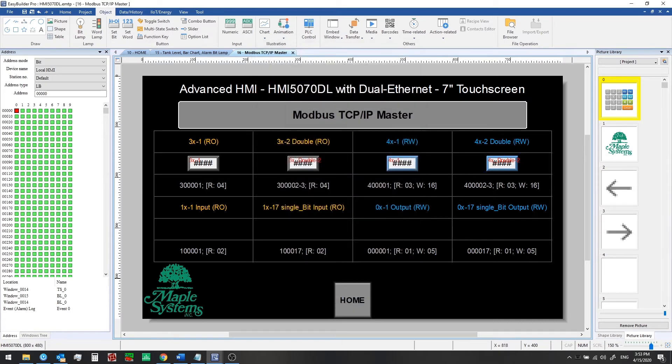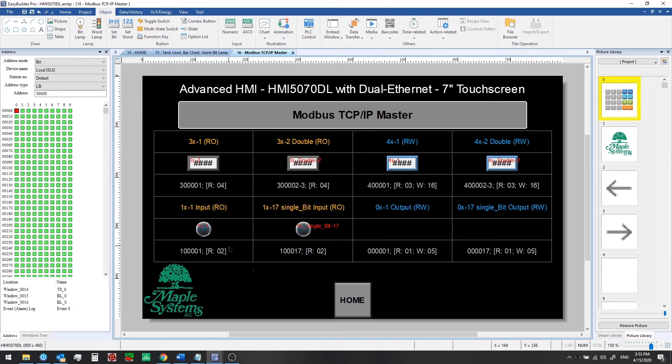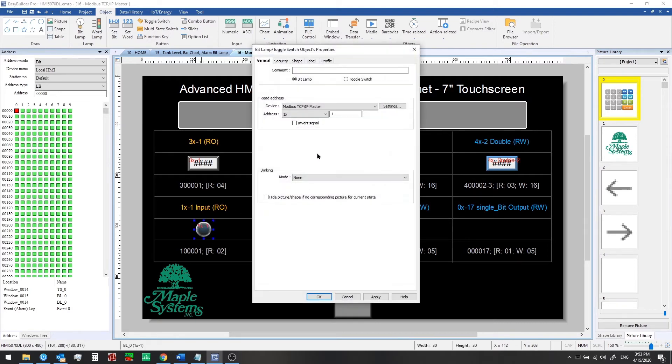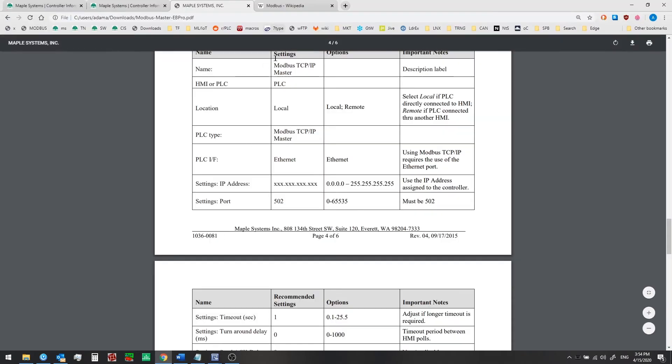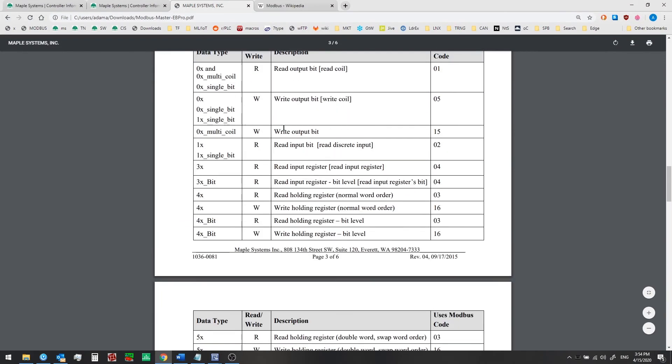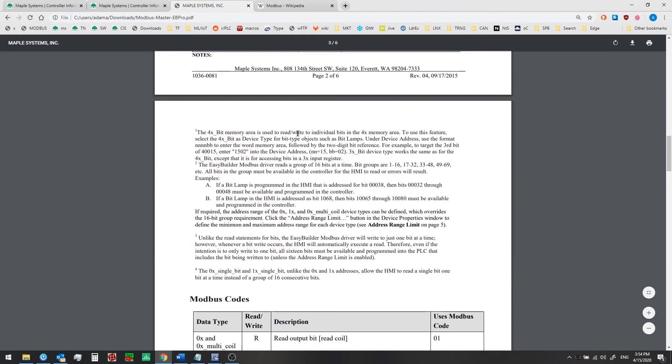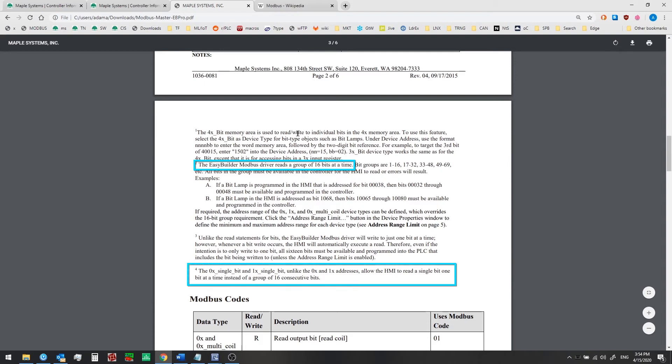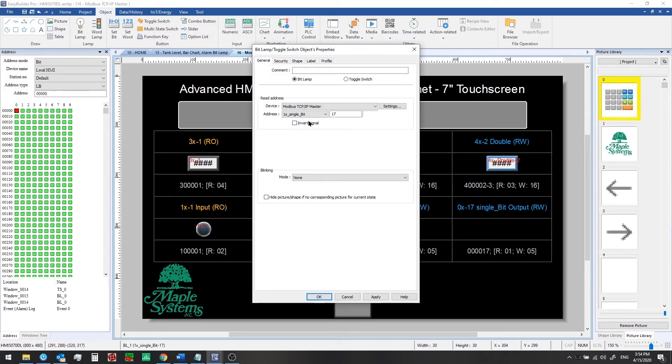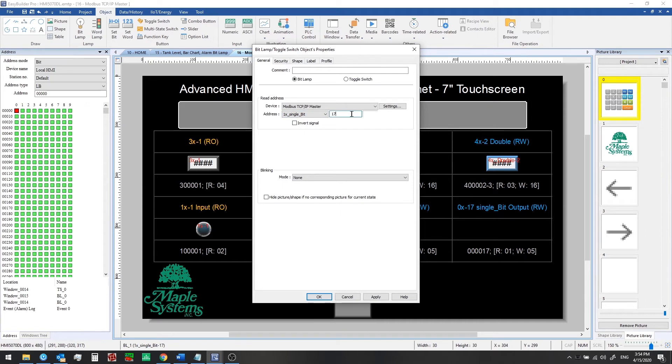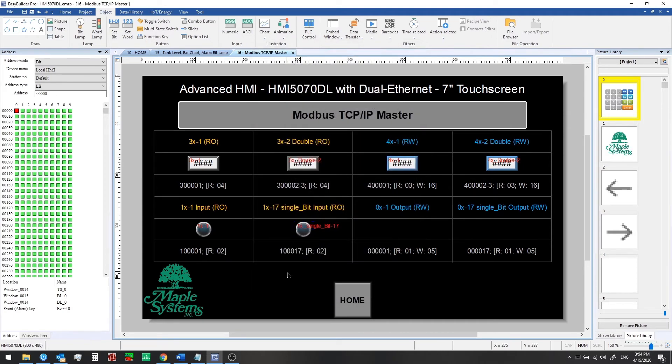Now we're going to add some bit lamps. These are going to be for discrete inputs. The first one is going to be a 1x1 or 100,001. When we do a read operation from our HMI, we are going to be reading 16 bits at a time. That's all described in the controller information sheet if you look at the notes under each section. Under the discrete memory, we have notes about this, and it says that we'll be reading 16 bits at a time if we pick the 1x or 0x. To get around that, if you have a single bit that you need to read and the other registers are not configured or not accessible, you can use the single bit type. Here we have an example of that. We're selecting 1x single bit 17, so we don't need 1x 18 to be available in order to be able to read just this bit from the PLC.